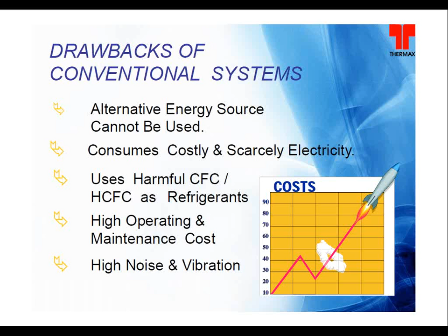Being a compressor, it is moving equipment. There is a high level of operating as well as maintenance cost, because you need to maintain the lubrication of this unit, as it is rotary equipment. Whereas the vapor absorption machine is stationary equipment. There is no moving component as such. These pumps are all canned motor pumps, like the absorbent pump as well as the refrigerant pump. So there is very little maintenance cost associated with the vapor absorption machine. Also, there is no noise and vibration for the absorption machine, whereas in electrical chillers, being rotary equipment, there will be a certain amount of noise as well as vibration.